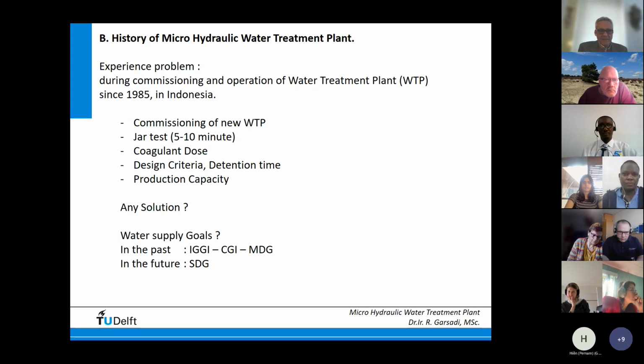I want to explain very fast, but from my history, I have experience since 1985. Yes, we had so many problems during commissioning, let's say the commissioning of a new treatment plant. It is really a problem to set up the first time, also if we don't know how to do the jar test. In my experience, in the jar test, a possible detention time of about 5 until 10 minutes gives a very good flow.